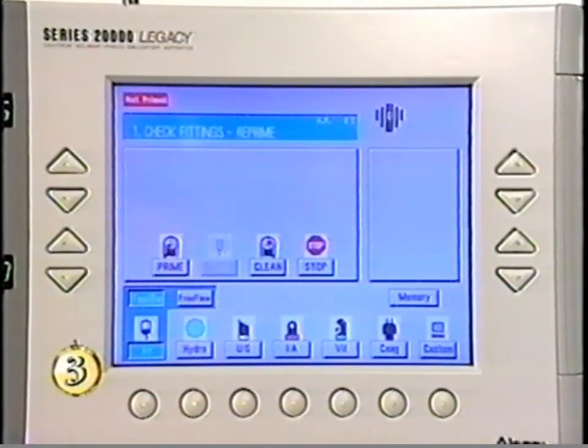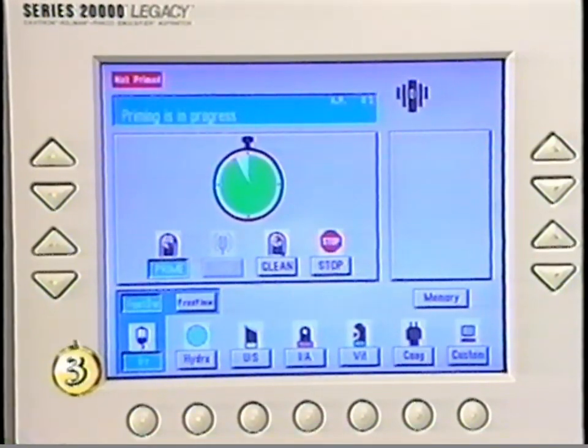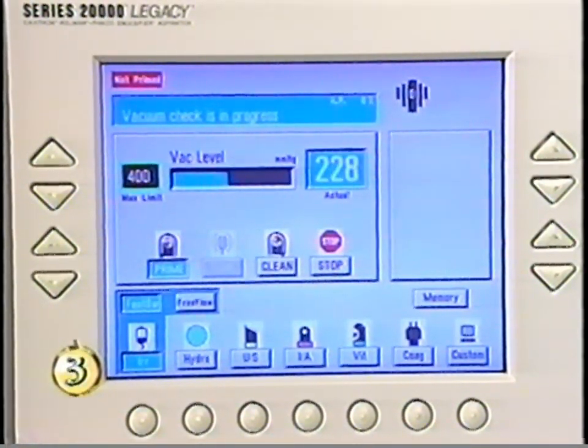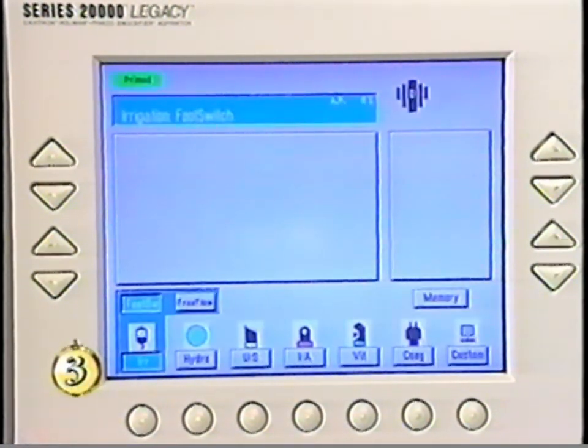If the vent test or combination vacuum and vent test is not successful, the system will restart the vacuum and vent tests after a brief delay. If these tests fail, these error codes will appear. Consult the troubleshooting section of the operator's manual for corrective action. After testing, the Legacy reverts to the irrigation foot switch mode, or the last mode displayed, and the IV pole drops to a programmed setting or the default position.